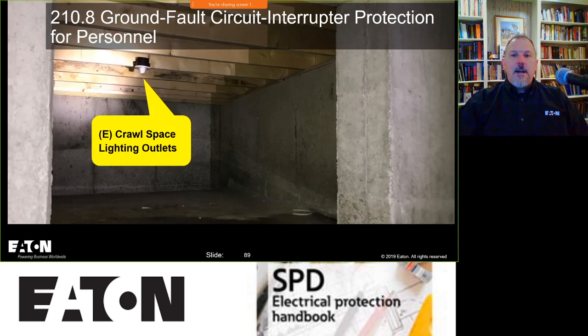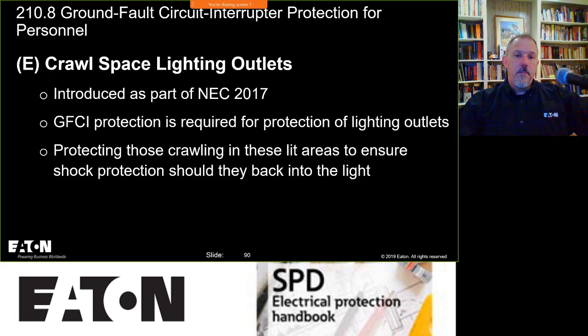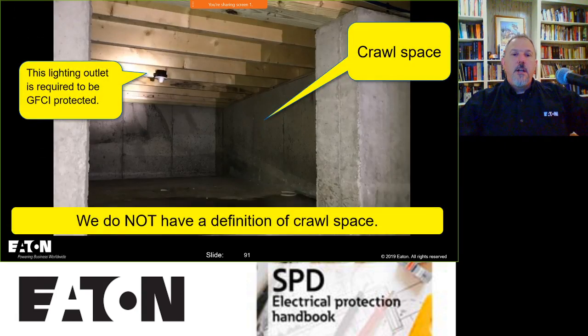Crawl spaces, lighting outlets. This is where you have an outlet - not a receptacle, an actual outlet - that's required to have GFCI protection. It was introduced in the 17 code, driven by the death of an electrical worker who was in a crawl space, backed up against a light bulb, and unfortunately was electrocuted.